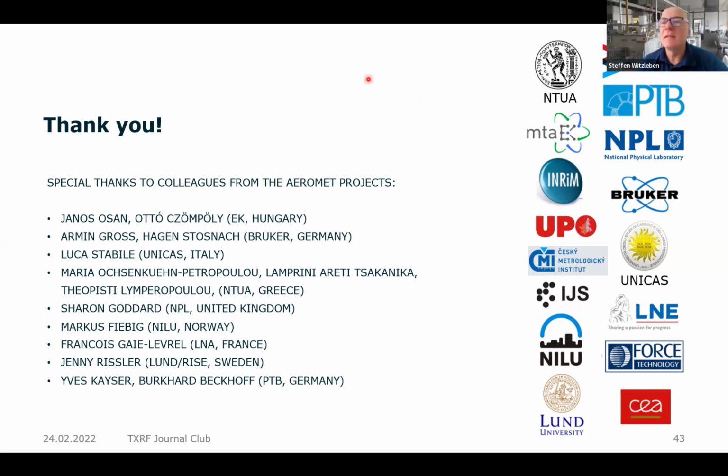Hi, Stefan. Thank you for the nice presentation and for really quite interesting information regarding dust measurements. I got one question regarding your comparison of ICP-MS and TXRF. I know in a lot of cases regarding ICP-MS, you measure recovery rates to test your equipment. It's a standard way. My question is, did you also try to measure recovery rates especially for the elements where there are some problems, like vanadium or chromium, in your measurement cycles?